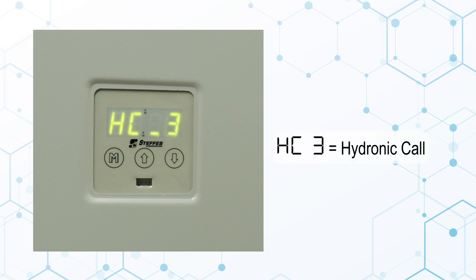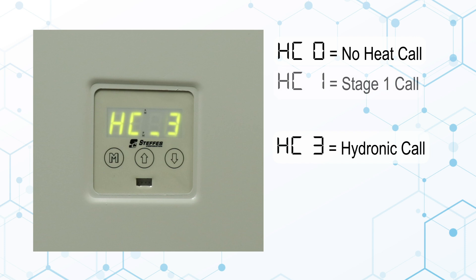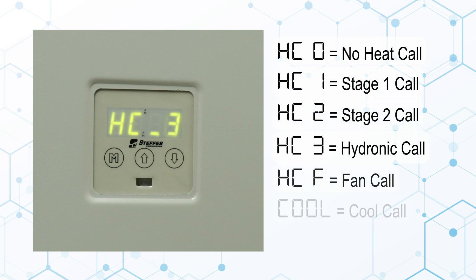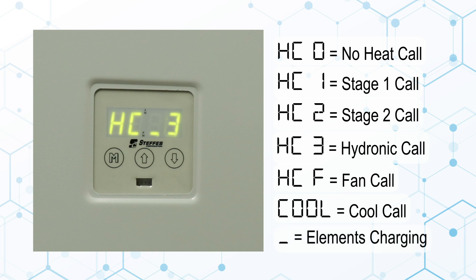HC3 indicates a hydronic heat call. If the hydronic system receives an additional heat call from an optional air handler zone, the faceplate will display the highest heat call value present. When heating elements are energized, an underscore illuminates on the display's third digit after the HC.